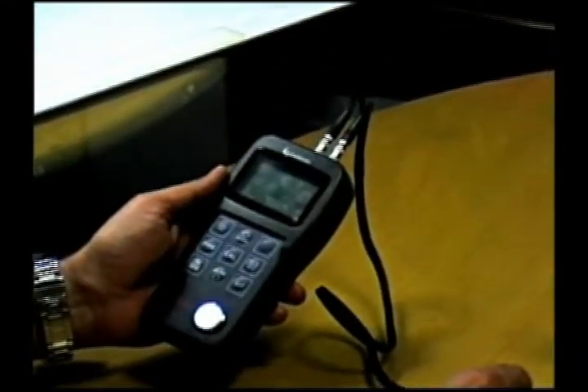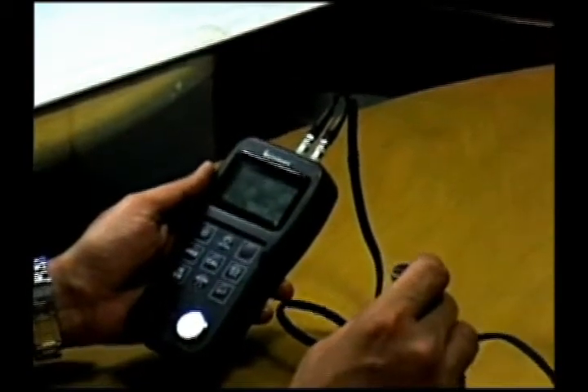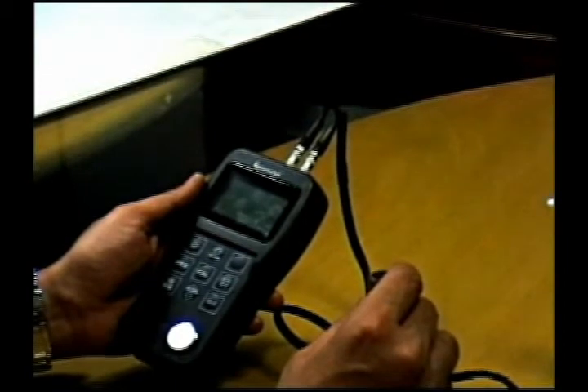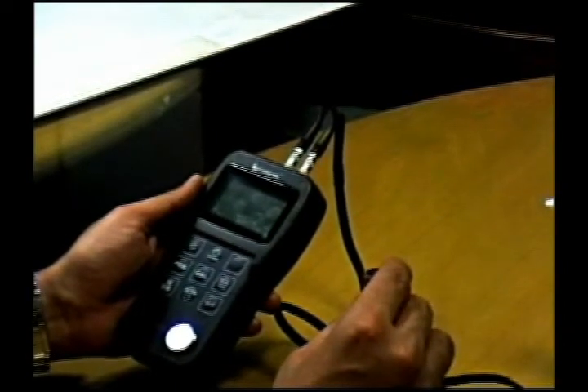The reason I mention the word ultrasonic is because the principle of the instrument is that it sends short ultrasonic pulses into the material whose thickness has to be tested, and it does so through what we call a transducer.